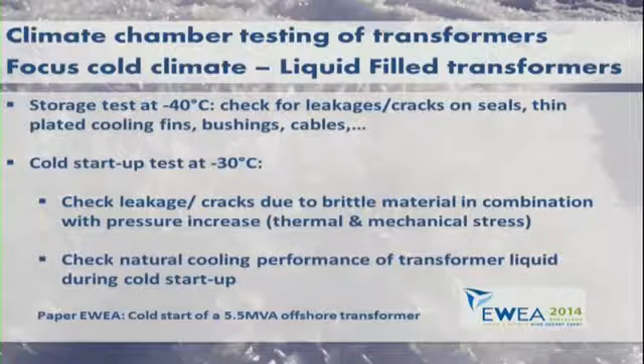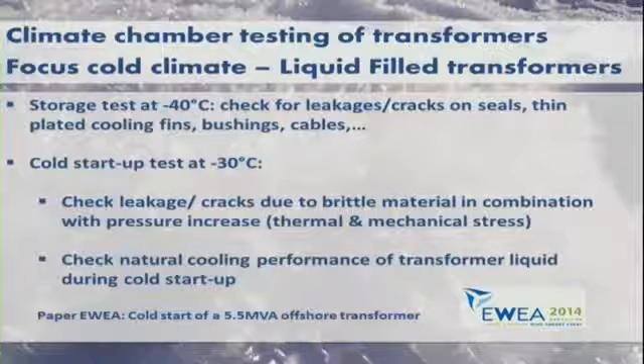Two cases to finish. The liquid filled transformer. Why do we do this test and what do we do? First, I already explained this. This is the storage test at minus 40, so we check leakage, and we check if there is any visual impact on the bushings, the cables and so on. And afterwards we do an operational test at minus 30 degrees, for example. Then again we check for leakage and we also check the cooling performance, so the natural cooling convection.